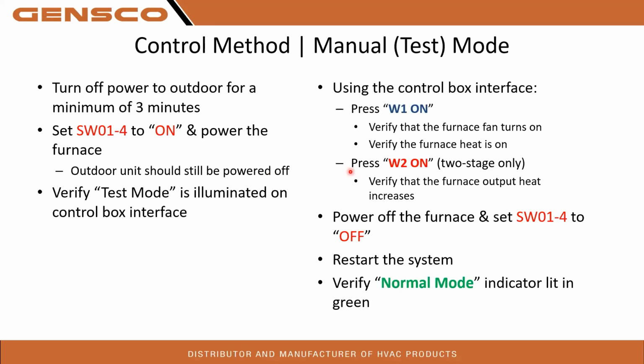To get it out of test mode, you're just going to power everything back off, turn SW01 number 4 back off, and restart the system and verify normal mode is indicated in green. One thing to note on these is if you're doing power cycles on the system, we need to treat this as if your indoor equipment is powered separately from the heat pump, meaning that your indoor equipment needs to be powered on before the heat pump is. So make sure to power up the furnace first and then the heat pump when you're doing power cycles to avoid any kind of communication issues.